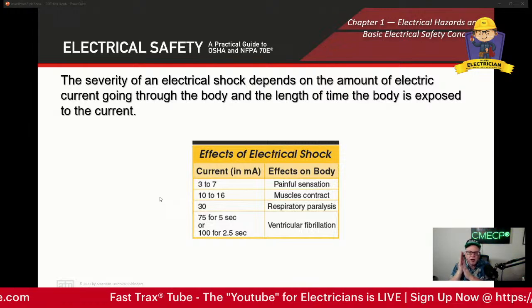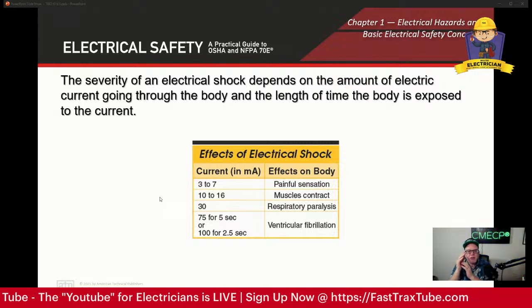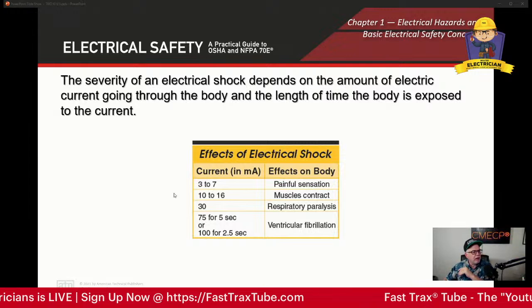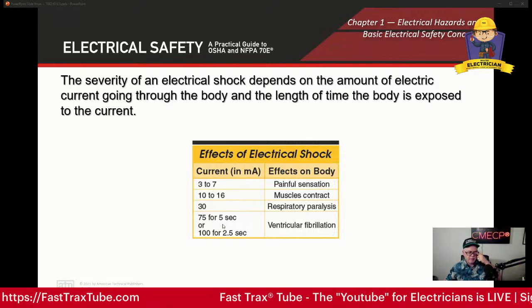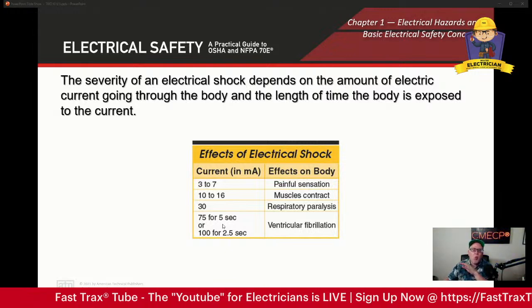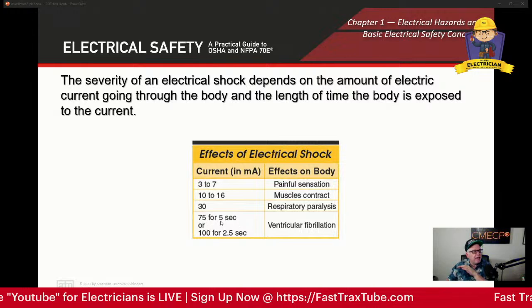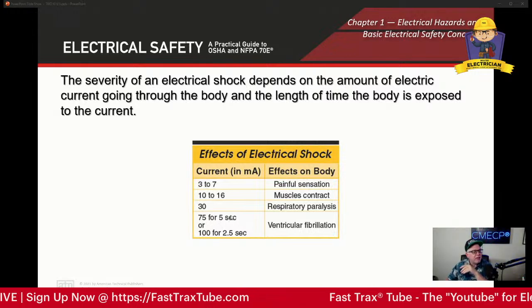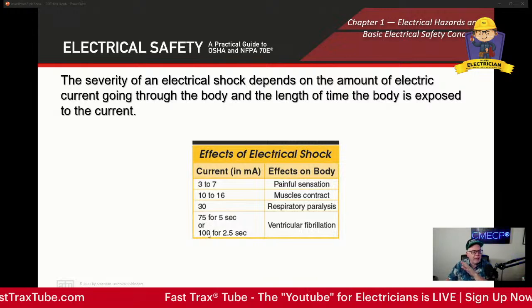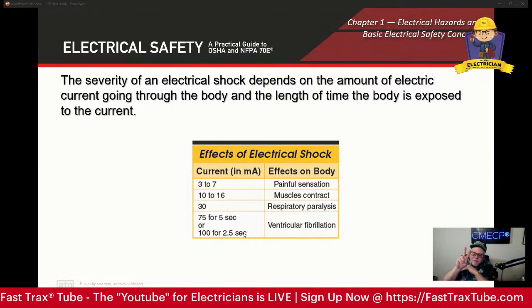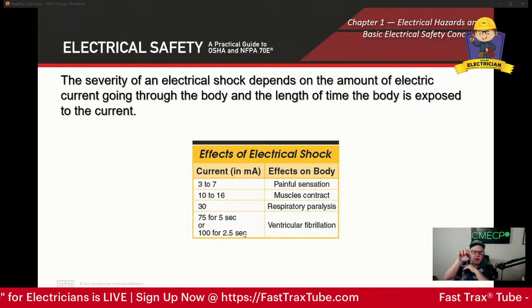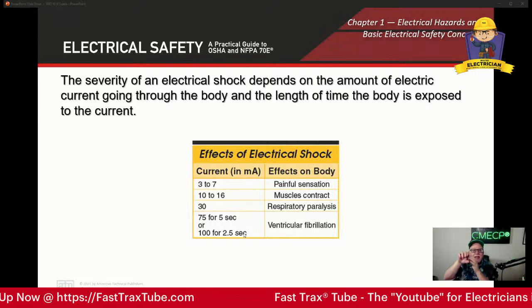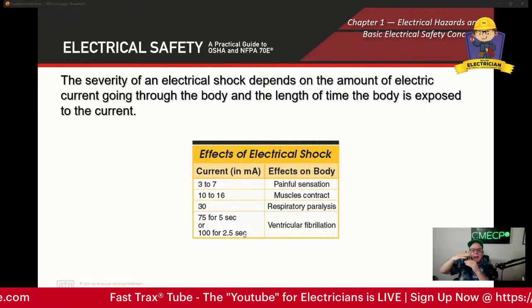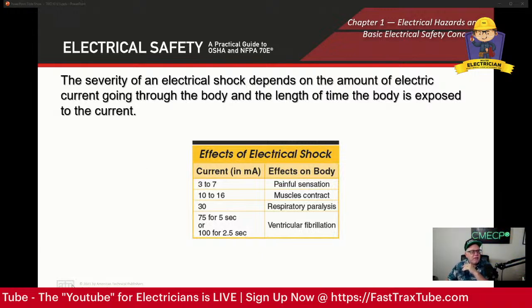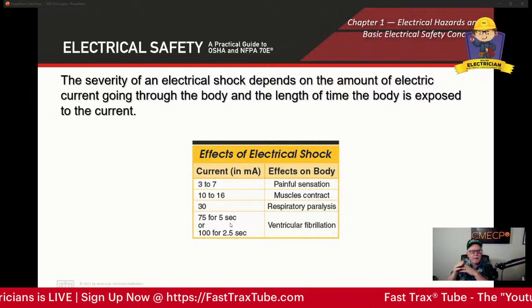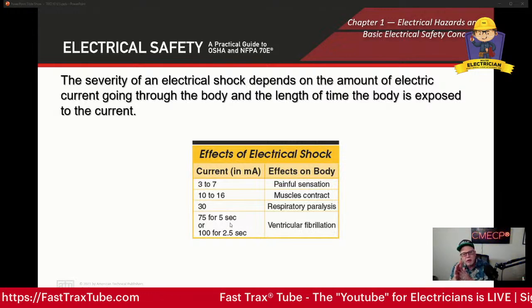That resistance that's inherent to us starts to be reduced, so current starts to flow a little bit easier. Now look at what happens if you increase that to 75 milliamps, again way below 1 amp. Here you're locked on for 5 seconds, or at 100 milliamps for 2.5 seconds. As you grab onto it, you could be at a lower milliamp level, but as you perspire, that resistance will drop and the milliamps will rise, and the exposure increases. The longer you hold it, the longer you're on it, then all of a sudden you go into what's called ventricular fibrillation.